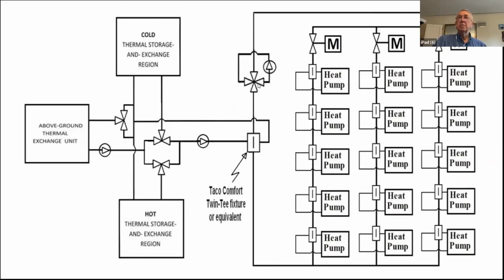And so let's assume the water is flowing upwards in this path. And then it enters in a pipe right here at the upper right in this design, and it flows into what's called a header pipe. And it flows through 3 additional valves that are computer controlled to make sure that we have an optimum flow rate in all 3 of these paths. So now the water will flow in a single pipe coming down this way and this way and to the right here. And each of these heat pumps will get either relatively warm or relatively cool water for providing whatever the building needs.